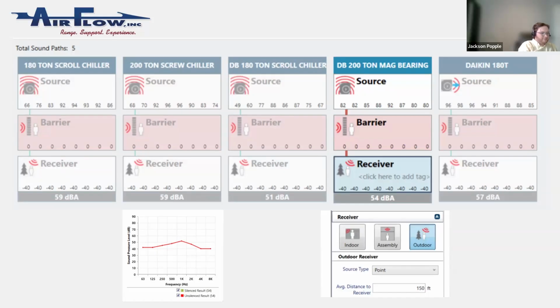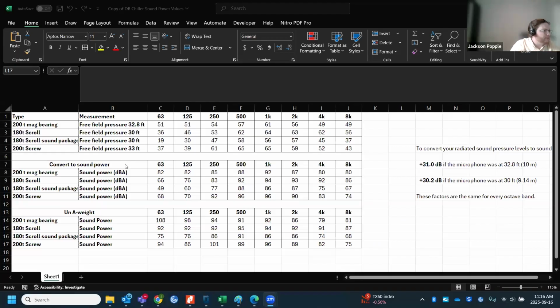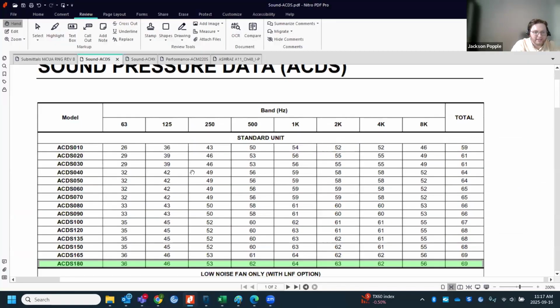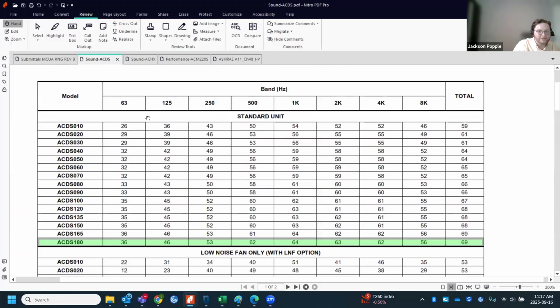Thanks, Tom. So I'm going to steal a screen here. Okay, perfect. Basically I took that same sound data that Tom had and also looked at it. The one thing I noticed was if you look at these values, and this is just the cut sheets for the sound pressure data we have, it's a lot lower in the 63 and 125 hertz bands than in these middle octave bands. That's usually not outright stated, but it's kind of a giveaway that these are actually A-weighted numbers.